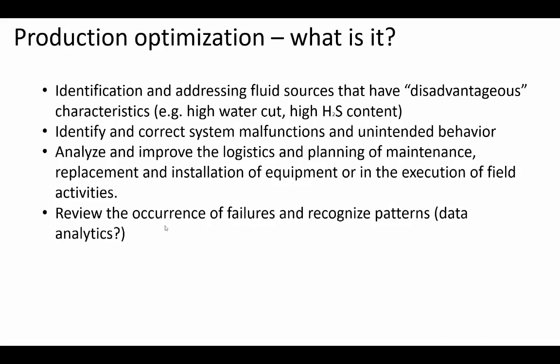You should also identify and correct system malfunctions and unintended behavior. For example, if an alarm is frequently triggering and causing plant shutdowns, you want to find out why it's happening. If it's a poorly set setpoint, you can correct it; if it's a real alarm, maybe you can change the equipment.